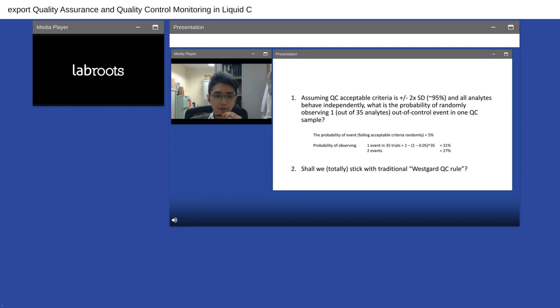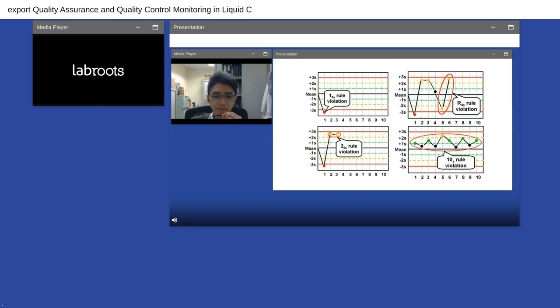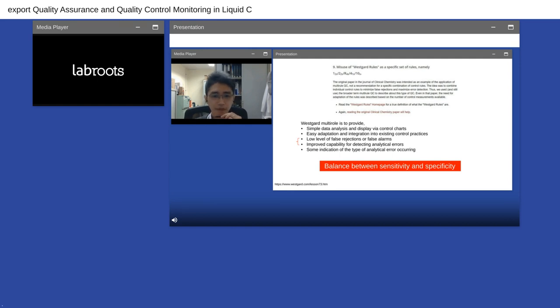Our laboratory performs a large number of these tests, and in each analytical run we typically observe one or two analytes outside the 2SD criteria. The question is whether to stick with traditional Westgard QC multi-rules. Going back to the original Westgard paper, the multi-rules — 1₃s, 2₂s, R₄s, 10ₓ — are not a gold standard that all laboratories must follow. Their main purpose is to reduce false rejections while improving detection of analytical errors, similar to how a reference interval interpretation balances sensitivity and specificity.